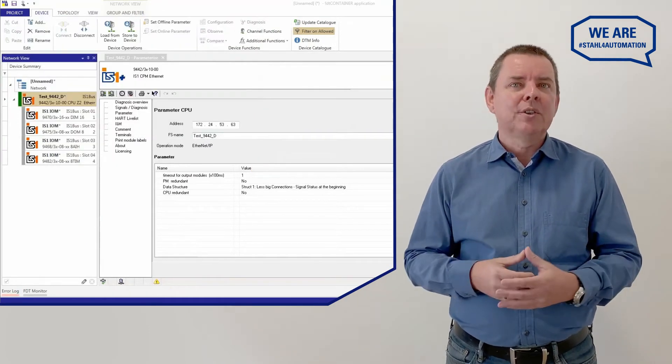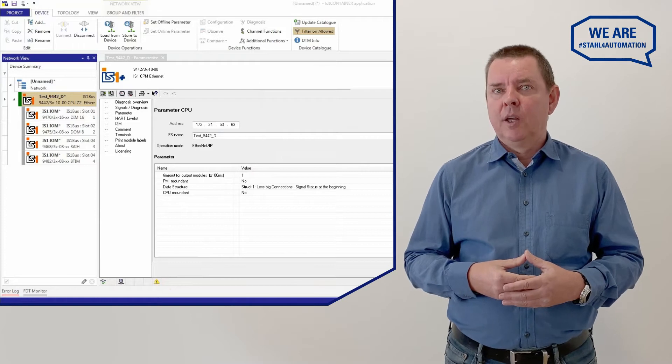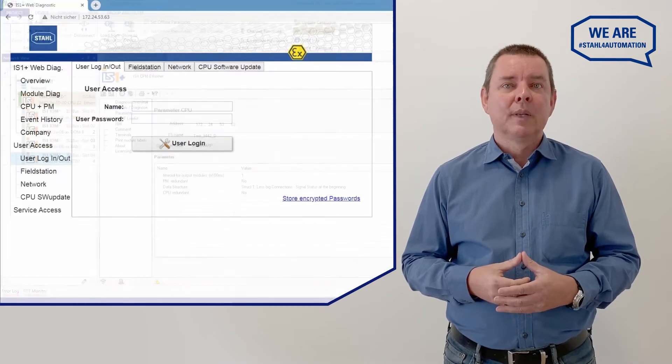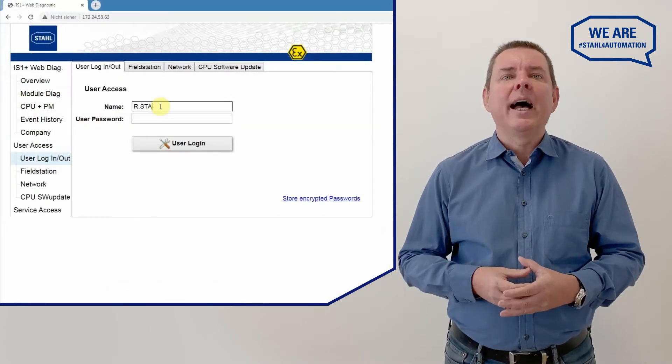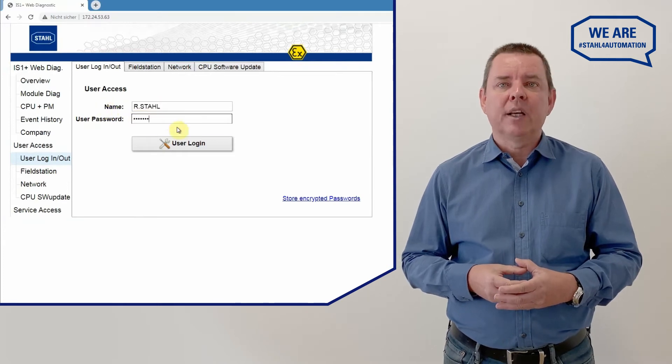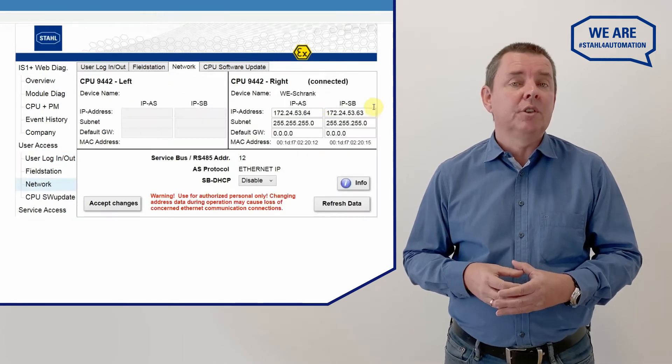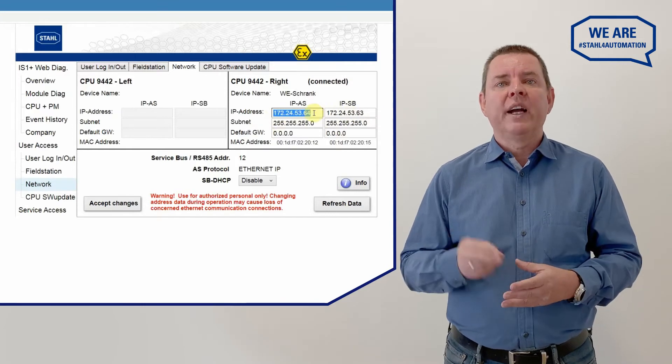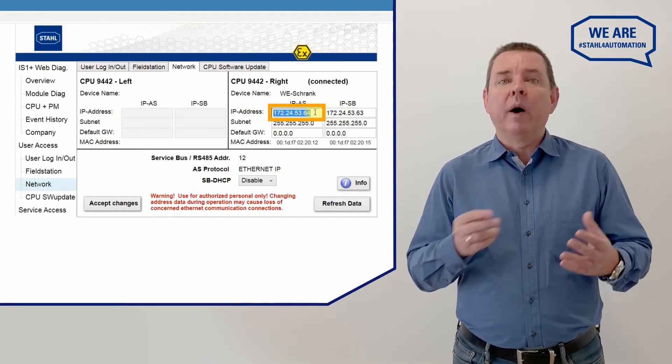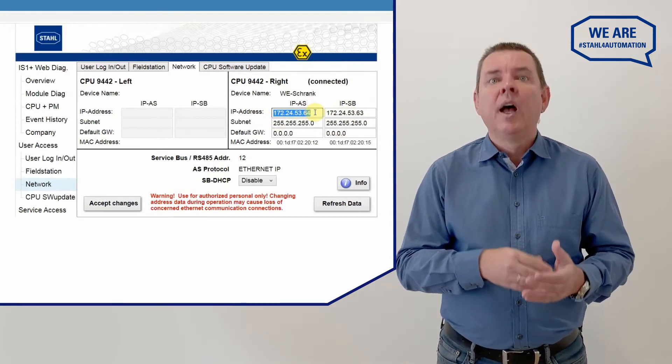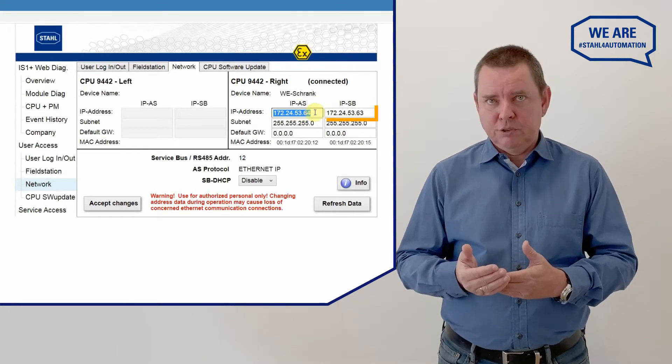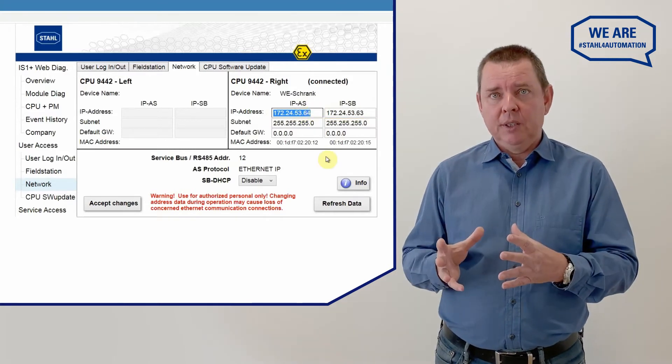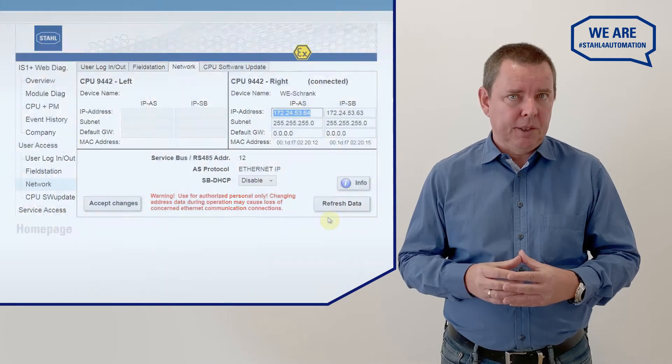Your RemoteIO is fully configured with the DTM. On to hook it into Rockwell. Before we need to set an IP address for the IS1 Plus service bus interface on the website of the CPU. 9442 has two IP addresses. One for connecting to the Rockwell system and one for the DTM service bus. Use different IP addresses but the same subnet.